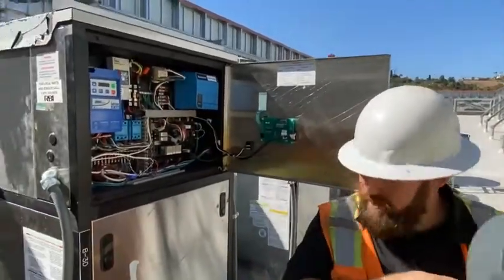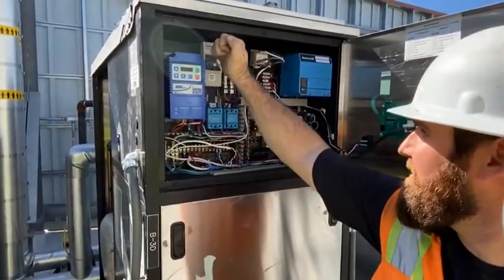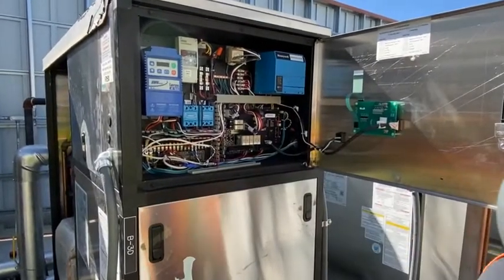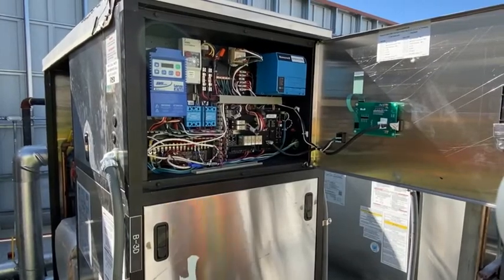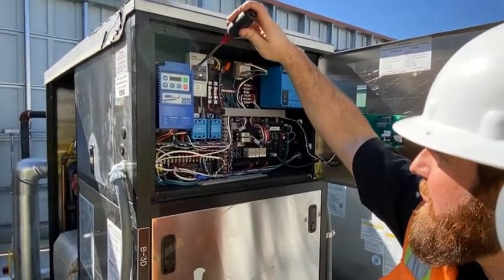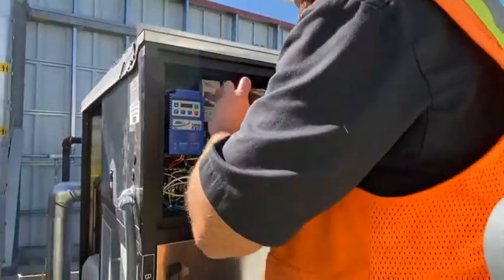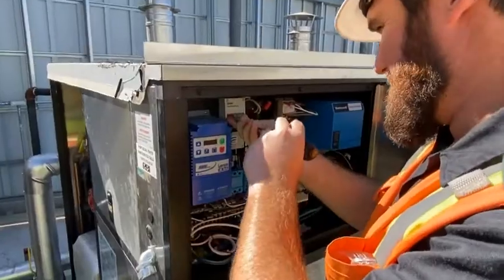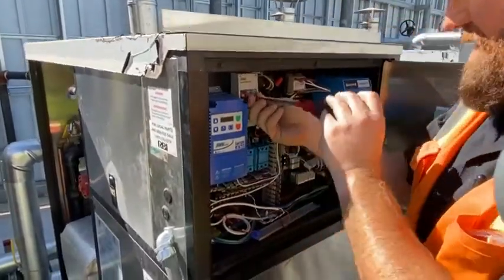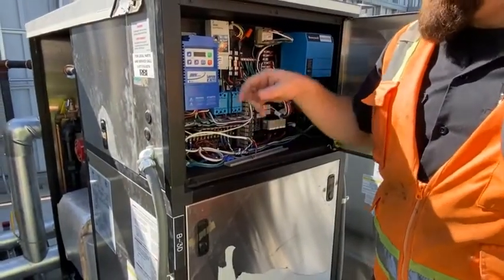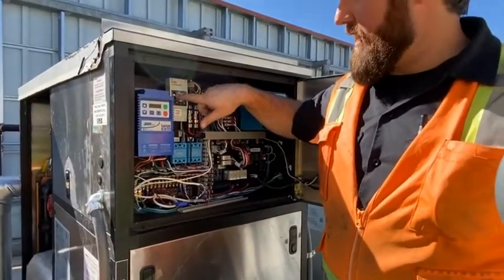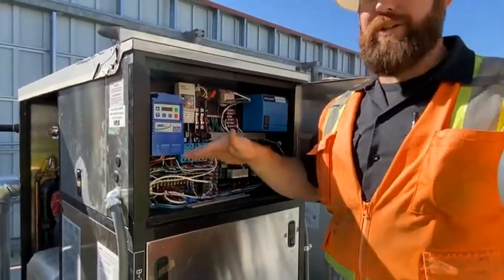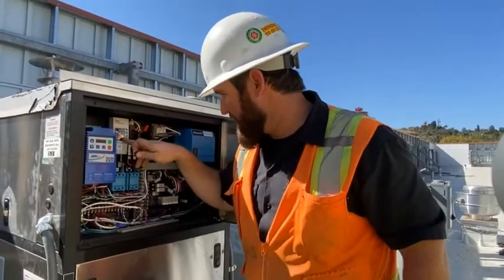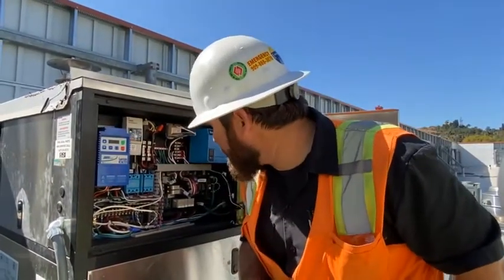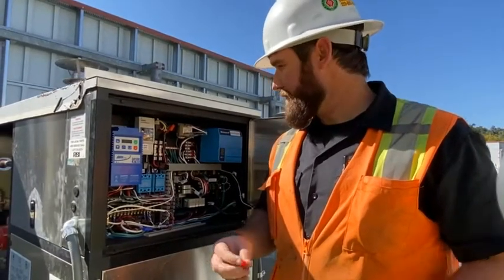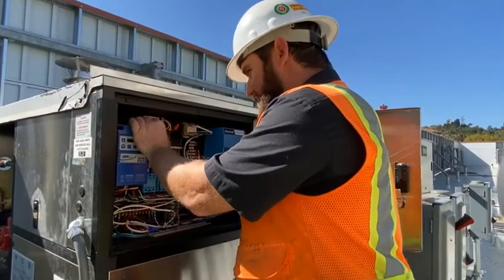This here is our high water or high temperature limit. You have to take that little red cap off and try not to lose it like I did. Then there's a little reset switch right here. You lift it up and it resets the unit as long as the temperature inside is below the set point, which is set at 235, 240. That's high limit.